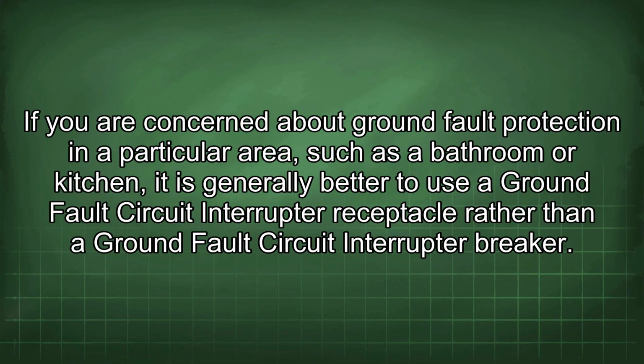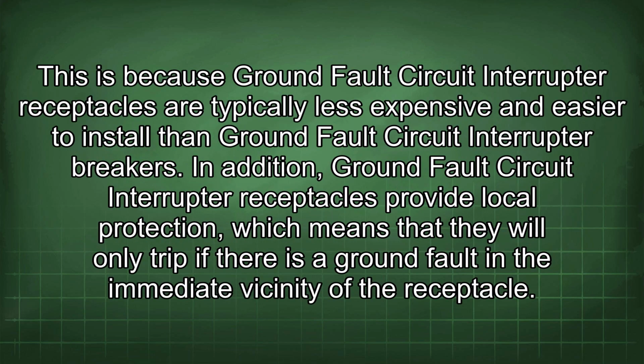If you are concerned about ground fault protection in a particular area, such as a bathroom or kitchen, it is generally better to use a ground fault circuit interrupter receptacle rather than a ground fault circuit interrupter breaker. This is because ground fault circuit interrupter receptacles are typically less expensive and easier to install than ground fault circuit interrupter breakers. In addition, ground fault circuit interrupter receptacles provide local protection, which means that they will only trip if there is a ground fault in the immediate vicinity of the receptacle.